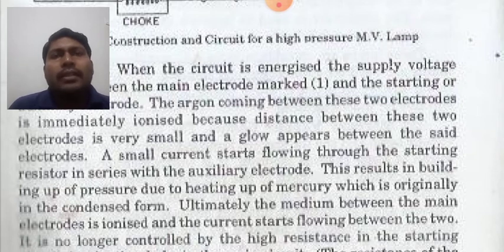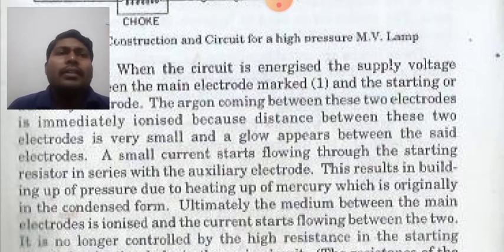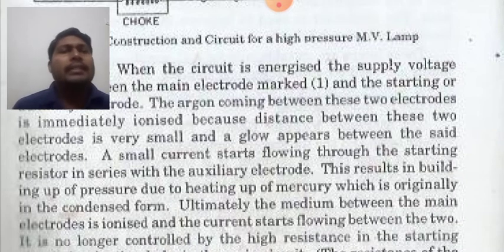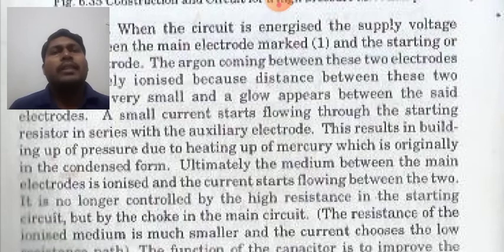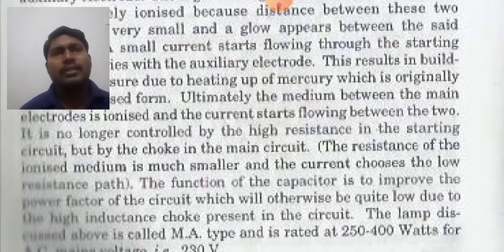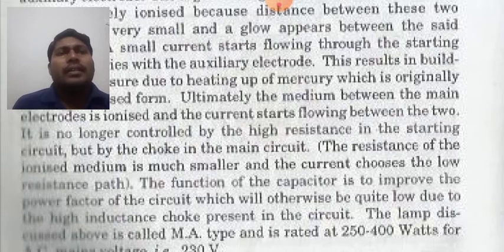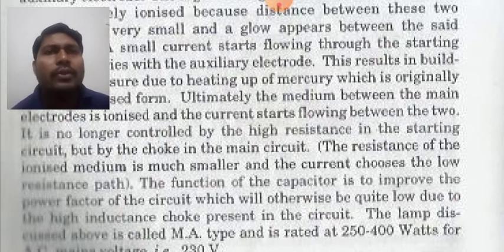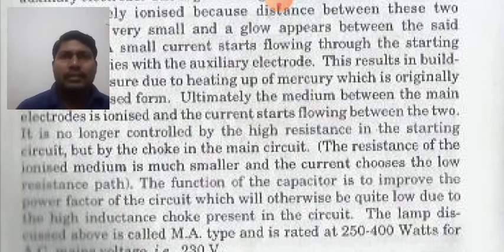Ultimately the medium between the main electrodes is ionized and current starts flowing between the two. It is no longer controlled by the high resistance of the starting circuit, but by the choke in the main circuit. The resistance of the ionized medium is much smaller and the current chooses the low resistance path.